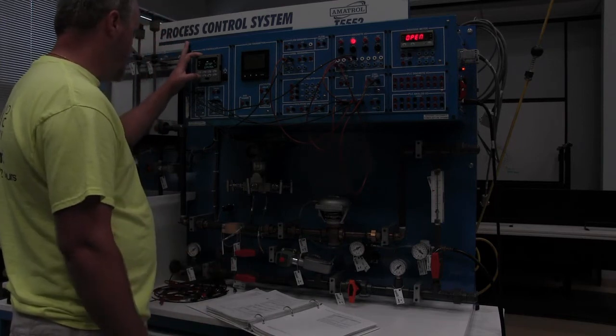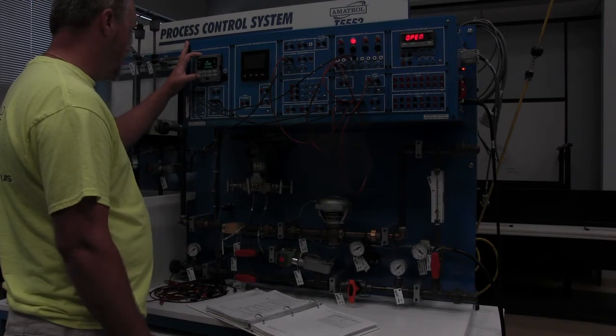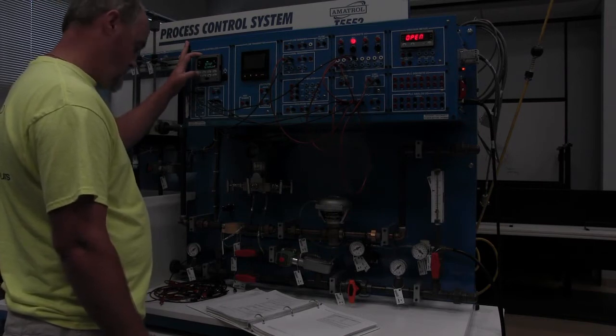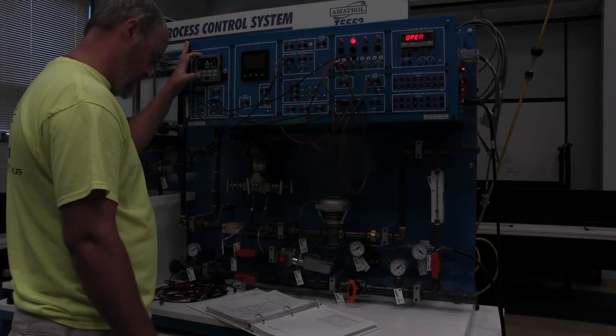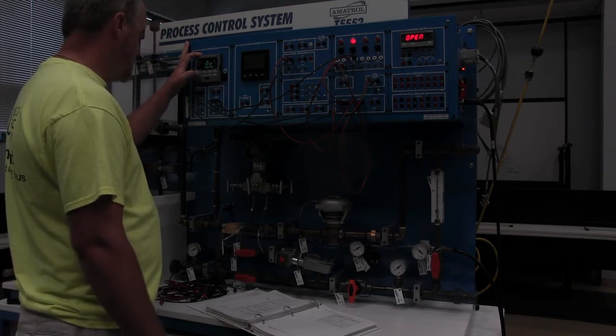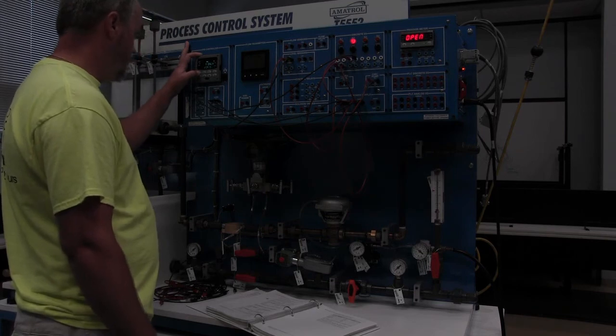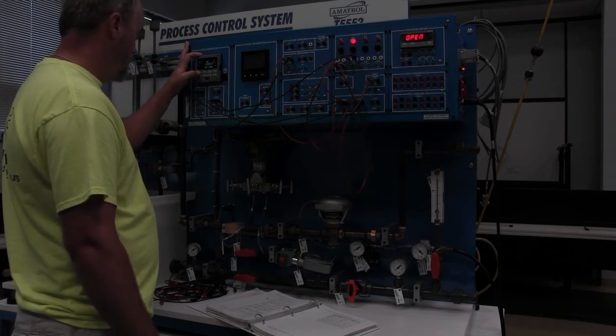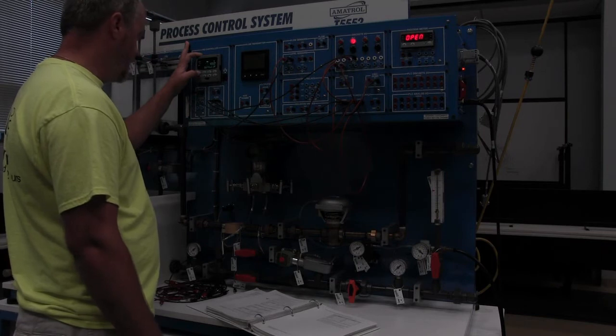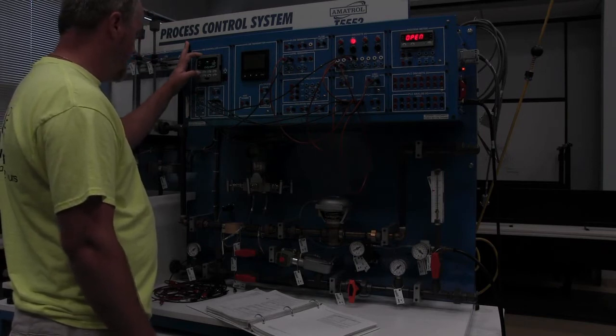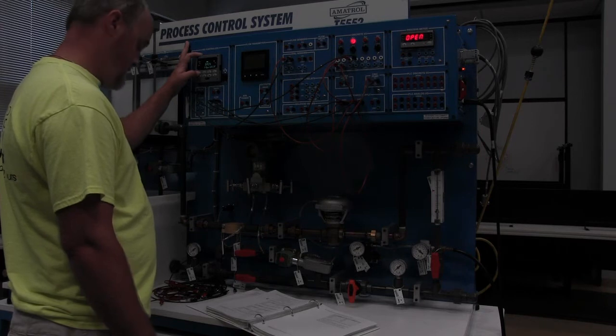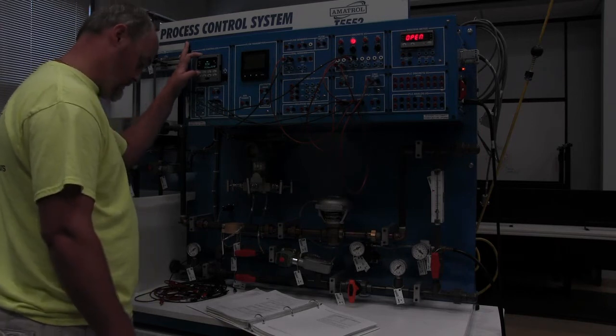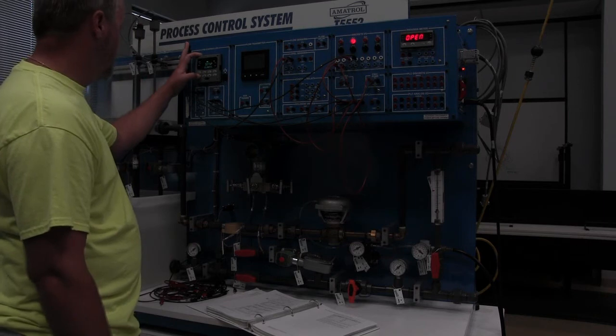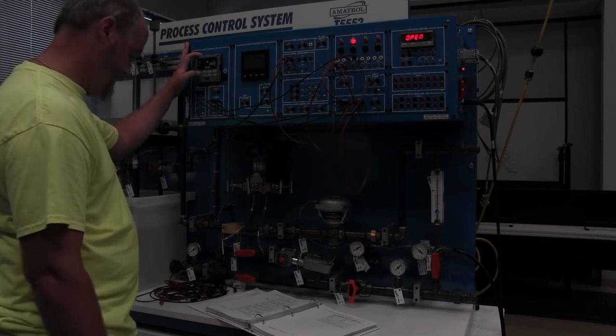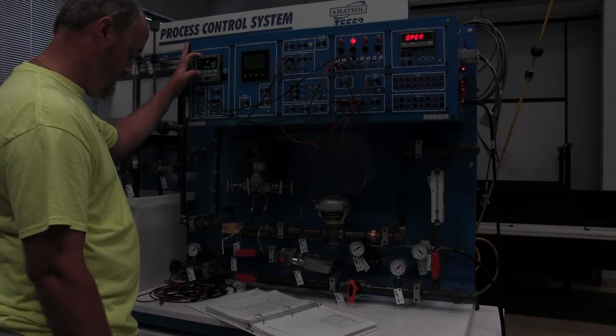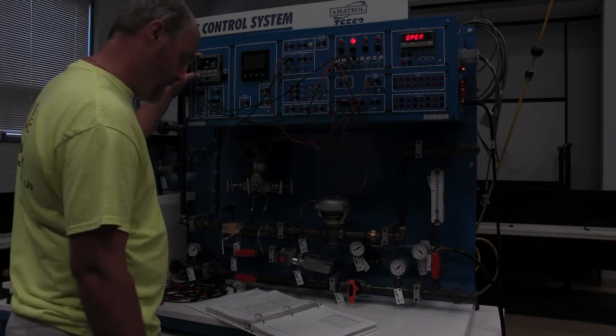Now we're going to go to algorithm, and we want PIDA, which is still set up. Control, we want direct. And we want gain, and we want min, so we're good to go there. Now we're going to go to tuning. This is the new one where we'll have to make changes. 20, 0, 125. No, that's not the new one. All right, so now we're going to go to alarms.